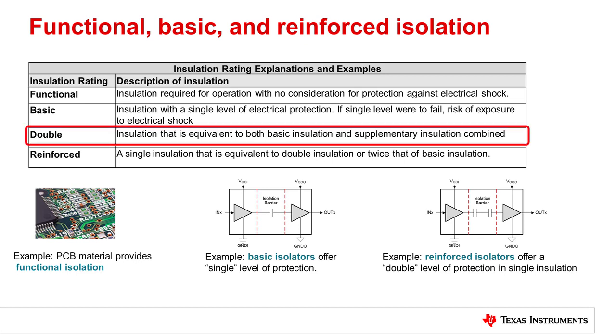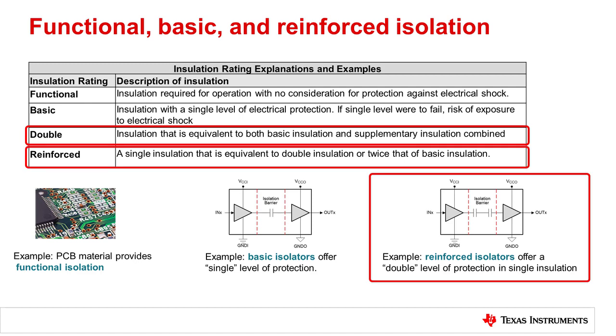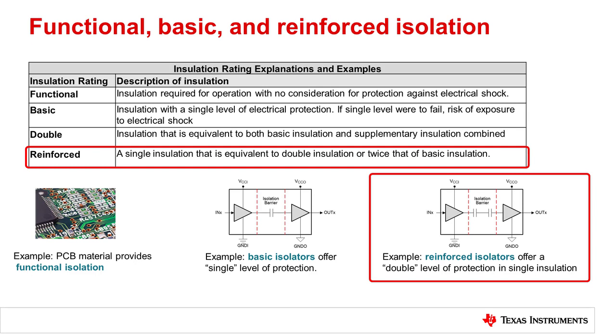This is called double isolation. Circuit designers can use two basic isolation components in series to achieve double isolation, or choose a certified reinforced isolation component. Reinforced isolation components may offer a single isolation barrier, but they must have the proven high voltage electrical strength, reliability, and shock protection equivalent to double isolation, or two levels of basic isolation.